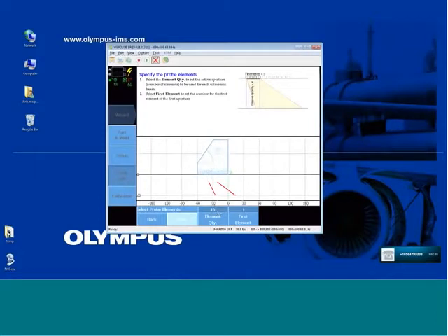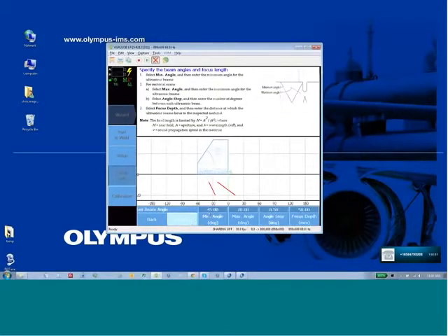And again, this is also limited by the instrument as well. A 16-128 instrument would not allow a quantity greater than 16 to be entered here. Select next. Enter our angular range, angle step and focus distance that we had just spoke about.